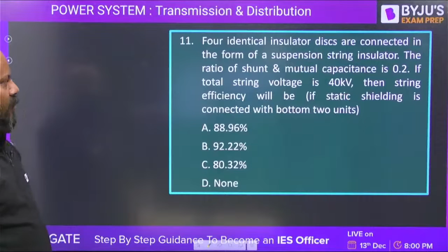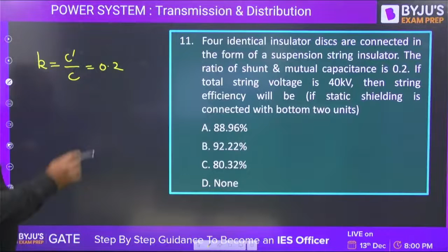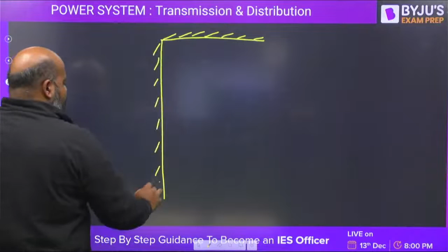See the next question. 4 identical insulator discs are connected in the form of a suspension type string insulator. The ratio of shunt and mutual capacitance is given as K, that is C dash upon C is 0.2. If the total string voltage is 40 kilovolt, then the string efficiency will be, if a static shielding, that is the guard ring, is connected with the bottom 2 units. So it's something like this. Suppose this is your suspension type string insulator.